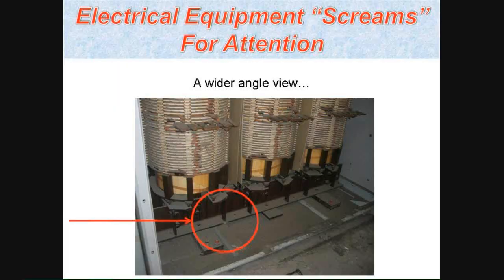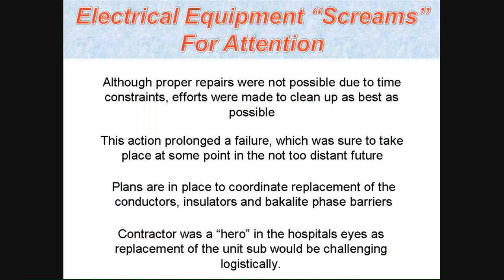And that's a wider angle view there of the transformer, just giving you an indication of the physical layout inside. It's a very large unit substation. So the proper repairs were not done at that time, but it was cleaned up enough to prolong the inevitable. But the parts are on order, and they're going to be planning a shutdown to do that correctly.